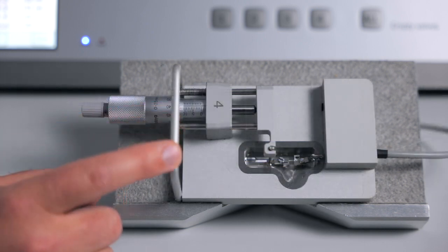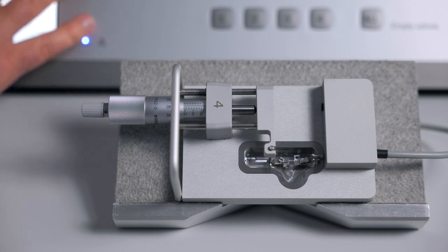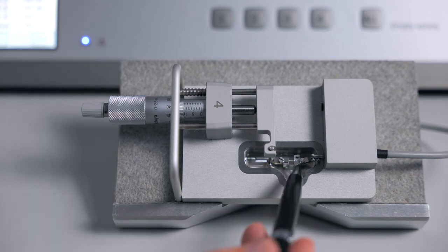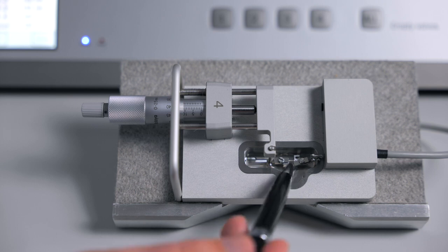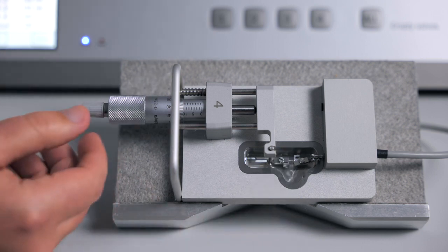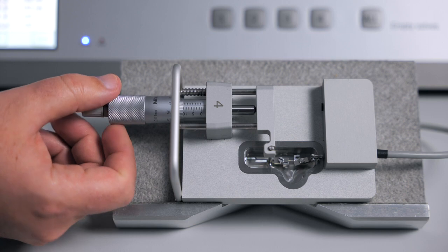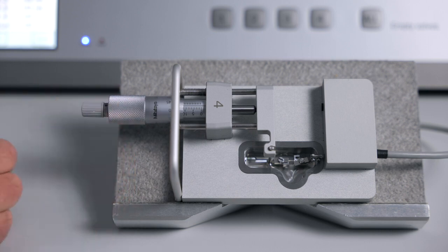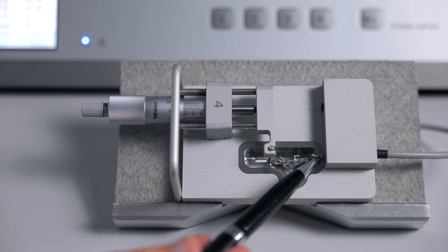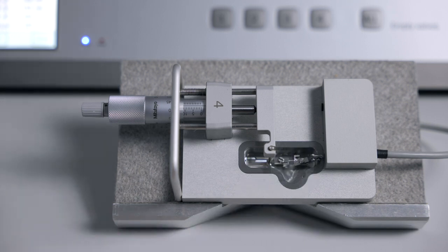The 820MO chambers can easily be removed from the interface and taken to a dissection microscope to facilitate tissue mounting. In the chambers themselves, there are 2 mounts. One mount is attached to a micropositioner or a micrometer, which allows for smooth and accurate tissue adjustment. The second side is connected to a force transducer, which will register the forces generated from your tissues during the experiment. The force transducer is the most sensitive part of the system and must be handled with care.